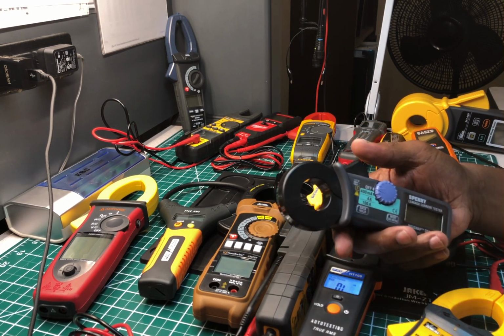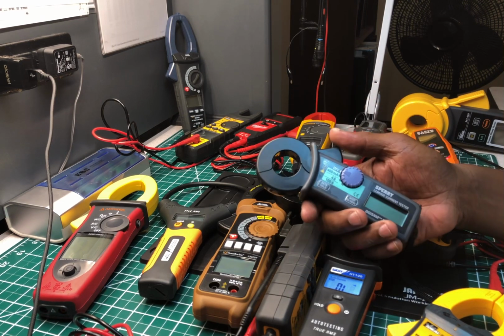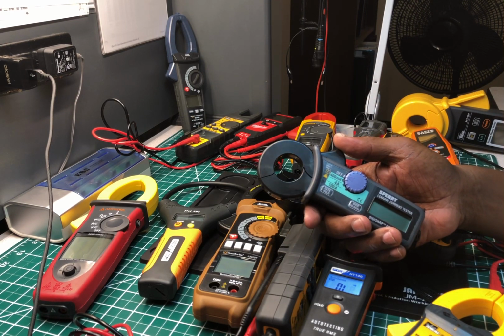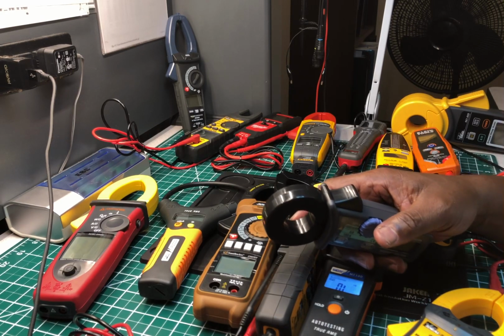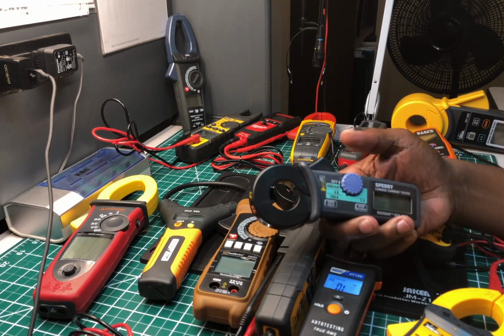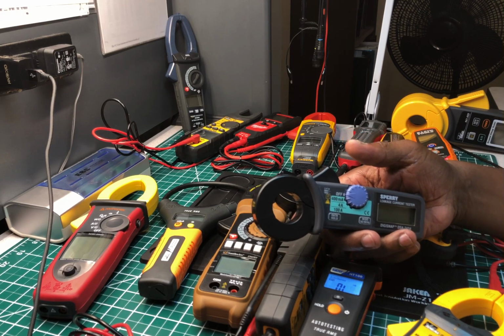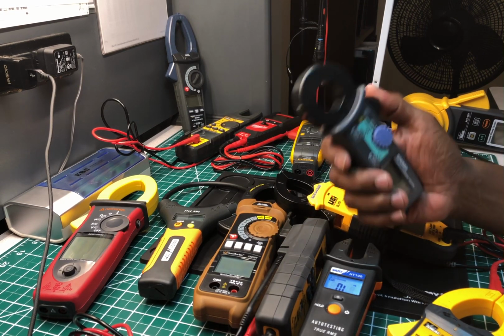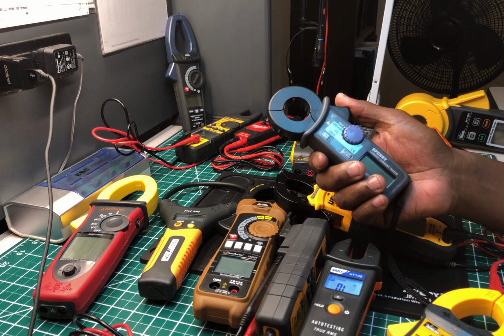It may be over 30 milliamps that's tripping your breaker. The breaker itself may be rated, let's say the GFCI is rated for 20 amps as an example, and you get 30 milliamps of leakage. Well, that's your problem, you just solved your problem.